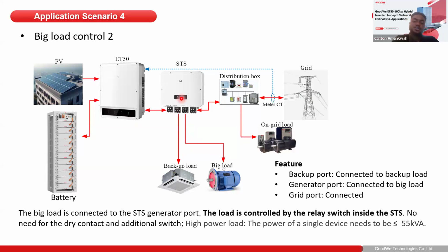So how does this system actually supply power to this? The STS itself comes with internal relays, and these internal relays control the power flow to this big load based on the configuration, just like how the inverter would start and stop the diesel generator. That's the same way the inverter will supply power to this big load, depending on how the system is configured.